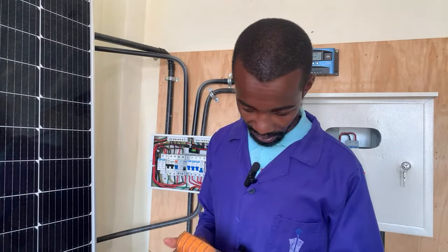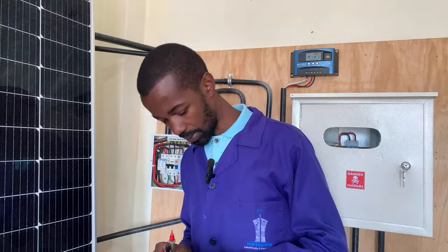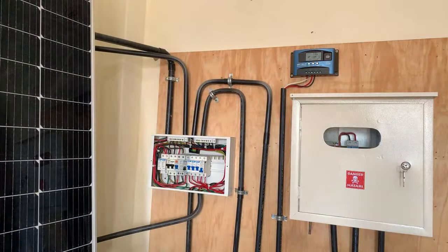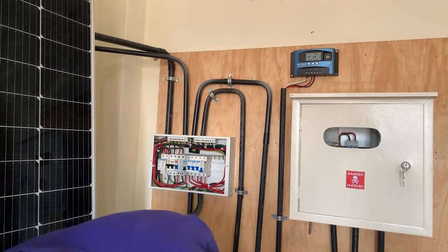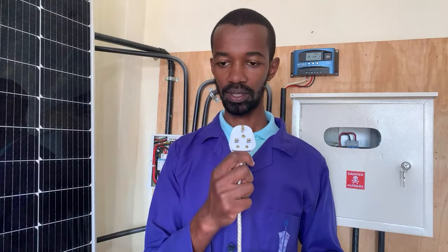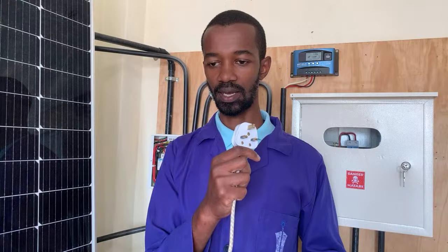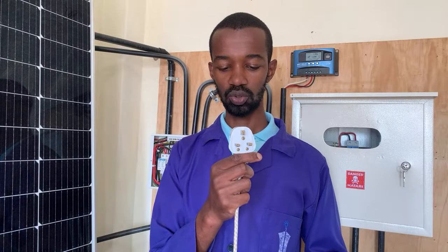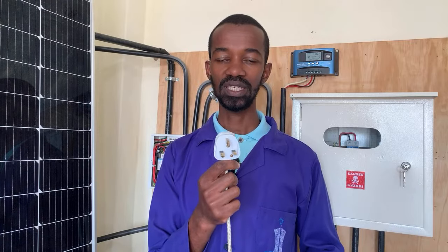In most cases, you will just take that plug. Let me have a plug here. So if it were me, I will simply take a plug. See, this is the top plug. We say that an electric cooker should not be plugged to the normal sockets. An electric cooker should be plugged to the cooker connector that is just below the cooker unit, and it is supposed to be switched by that heavy gang, which is actually a DP switch, a double pole switch, meaning it switches both the neutral and the live.